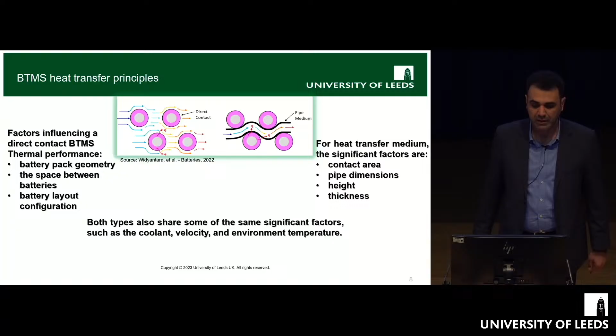There are factors affecting the performance of direct or indirect cooling with a medium. Battery pack geometry, the space between batteries, and battery layout configuration will significantly affect the performance of the battery thermal management system. When there's a medium for heat transfer, the contact area is quite important, as are the pipe dimensions, height, and thickness. There are also fluid mechanic criteria important in both cases: the type of coolant used, the velocity, and the environmental temperature all have a significant effect on the performance of the thermal management system.